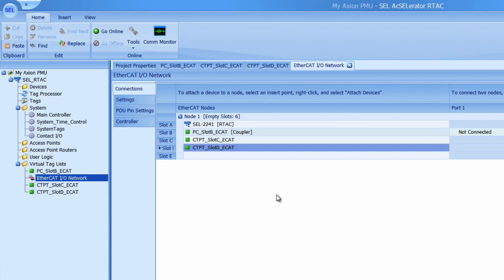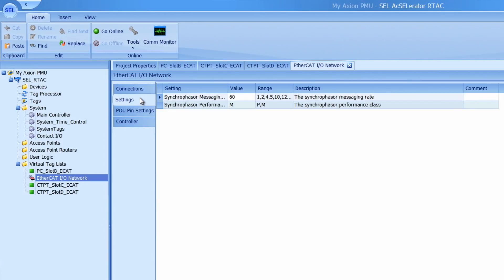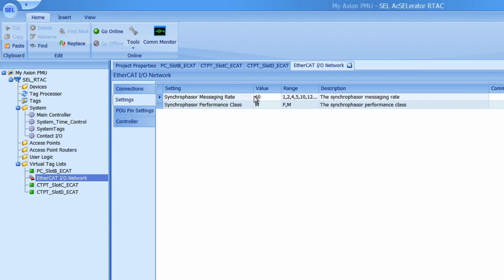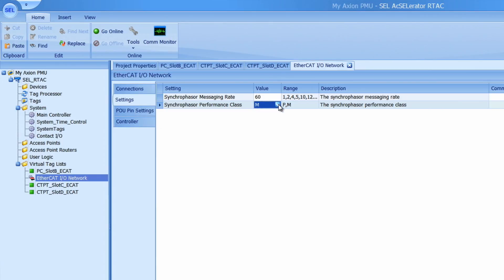One other setting I need to worry about for the EtherCAT IO network is in this settings tab we have the ability to change the synchrophasor messaging rate and the synchrophasor performance class. I want to use a messaging rate of 60 messages per second so I'm going to leave that as it is but I'm going to change the performance class to P for protection class. I'll hit ctrl s and lock that setting in. Okay so our EtherCAT network is ready to go.